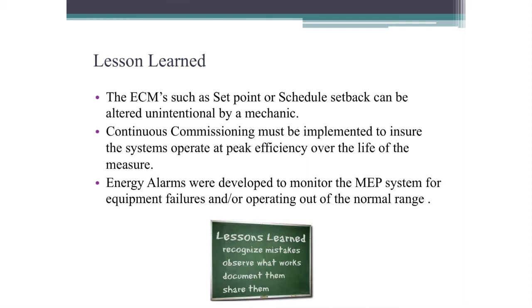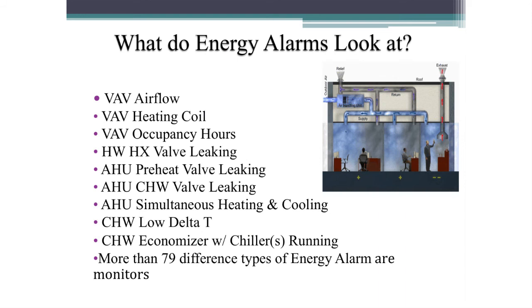We have an intern, and we generated all of these energy alarms. I think we have the same picture up there too. We look at the VAV airflow to make sure it's turning down. We look at the heating coil to see if the reheat's leaking by. We look at the occupancy hours to see if the mechanic has overridden it. We look at air handler leaking valves, simultaneous heating and cooling. We've generated, this is an old slide, but we've generated over 100 energy alarms that automatically will alert our intern and he starts to dig into it.